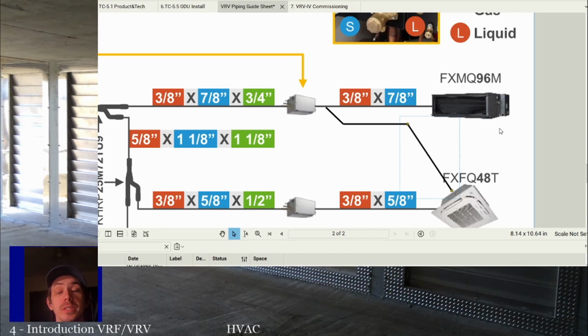So the whole system can run in heating and cooling simultaneously, right? But the branch selector is what determines whether an individual unit or set of units runs in heating or cooling. So if multiple units are fed off of a single branch selector, then all of those units have to be running in heating or cooling together.